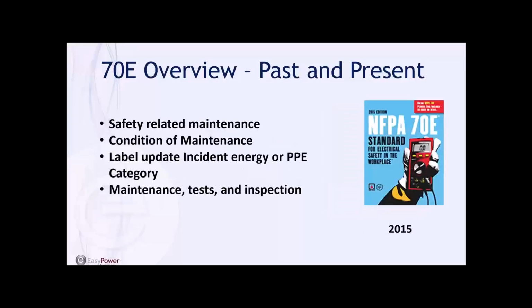The 2015 standard brought a real key step forward. When you think about it from an arc flash perspective, it's the guts of electrical equipment — the wiring, terminations, and devices — where an arc flash event will occur. It doesn't occur on the label on the front of a piece of equipment. So safety-related maintenance and condition of maintenance, focusing on the electrical equipment, distribution equipment, and infrastructure, is one of the key elements of the 2015 standard.